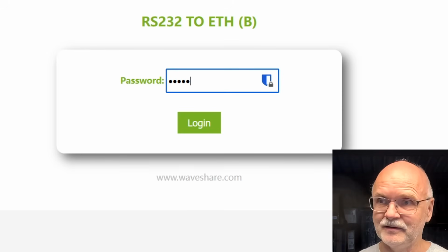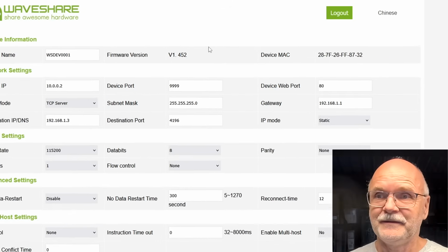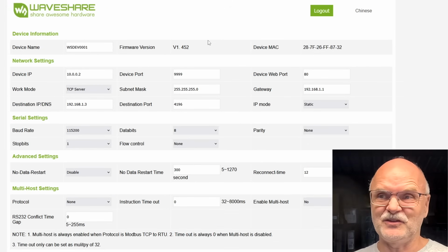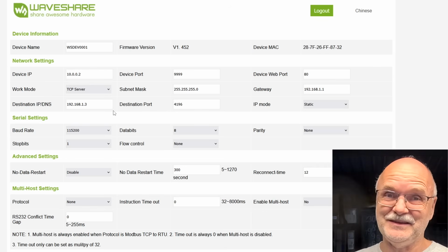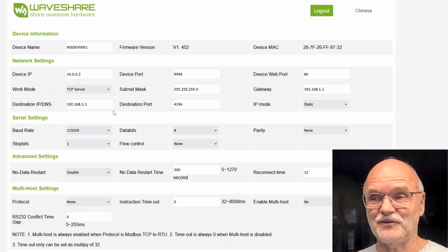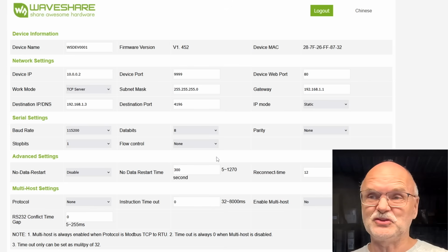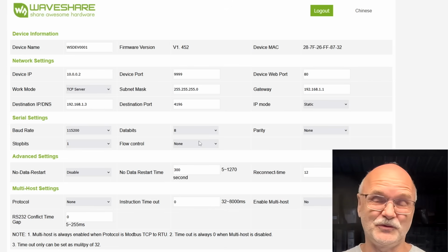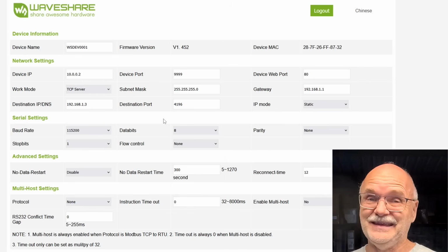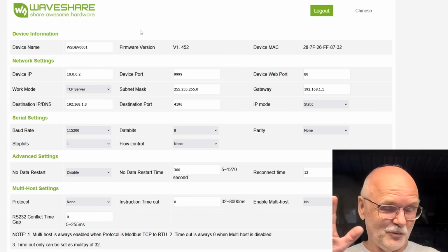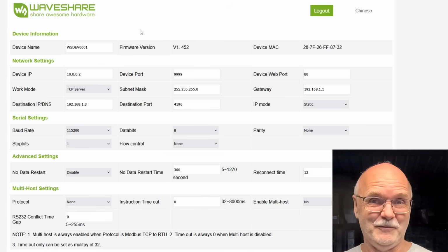I type in the password admin, and you're in the configuration as well. You can see the exact same parameters as we just saw in the VirCom software, and there's nothing you need to change here. This just proves your Modbus gateway is correctly configured. It is now on your network, it is accessible, and this is all you need to do with this device. You're completely set up now.